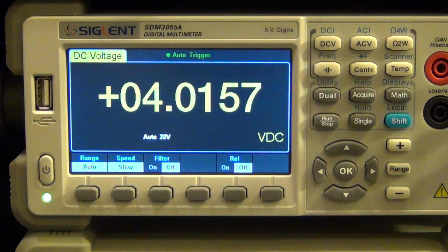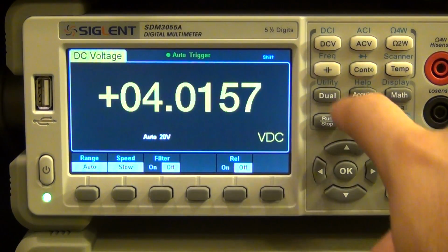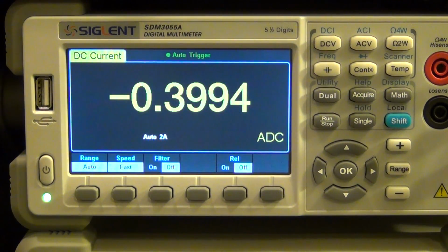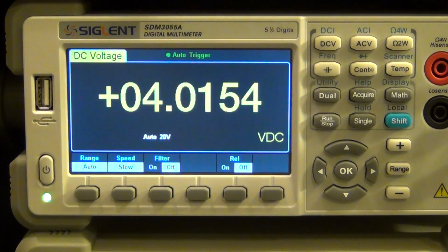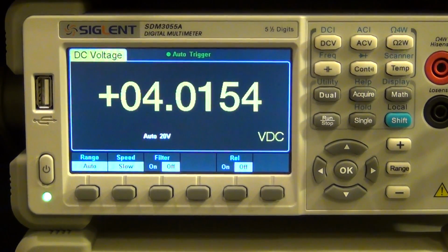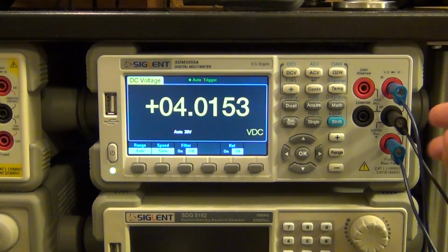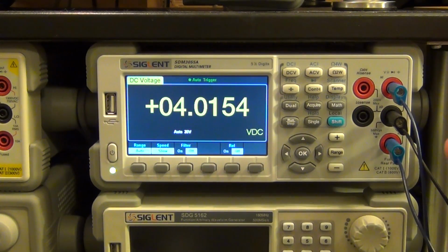And if I want to measure the current, that's also really easy. I just press shift and DC current, and there it is, and you can see the current is 399 milliamps or so. Again, very straightforward. And this is always live. I can always go back and forth between these two measurements without any issue, because the circuit is closed directly through the relay, through the shunt resistor that is inside the instrument for measuring current.